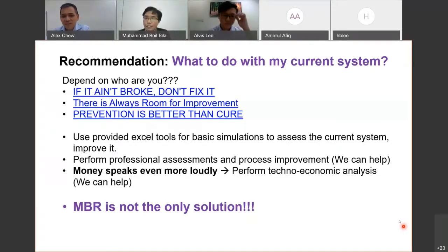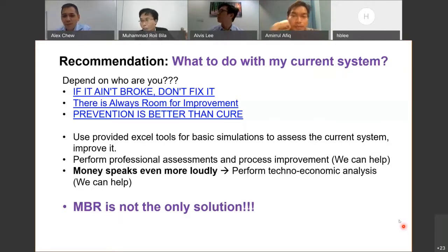The reason is that we operate the system at a longer retention time, which we call the sludge age, or sludge retention time. When you operate sludge at a long retention time, you have higher endogenous respiration. So the cells will eat themselves, instead of growing and producing more sludge. If you look at the F to M ratio, the ratio of food to microorganisms for MBR is very low.